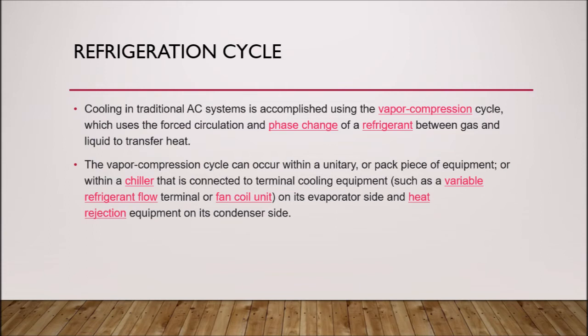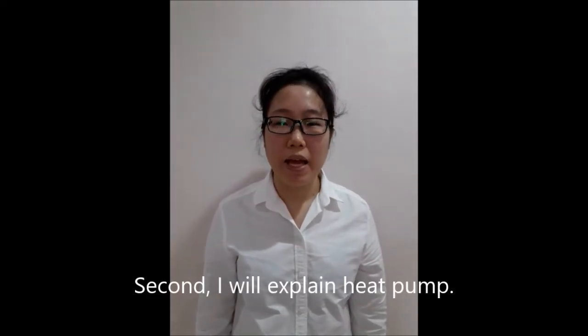Refrigeration cycle. Cooling in a traditional AC system is accomplished using the vapor compression cycle, which uses the forced circulation and phase change of a refrigerant between gas and liquid to transfer heat. The vapor compression cycle can occur within a unitary or packaged piece of equipment or within a chiller that is connected to terminal cooling equipment such as a variable refrigerant flow terminal or fan coil unit on its evaporator side and heat rejection equipment on its condenser side. Second, I will explain the heat pump.